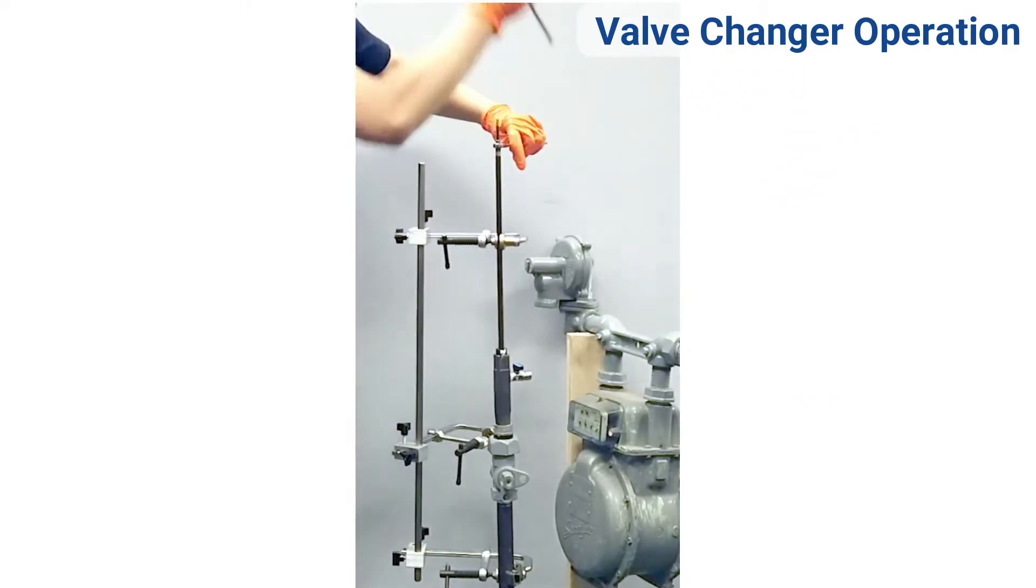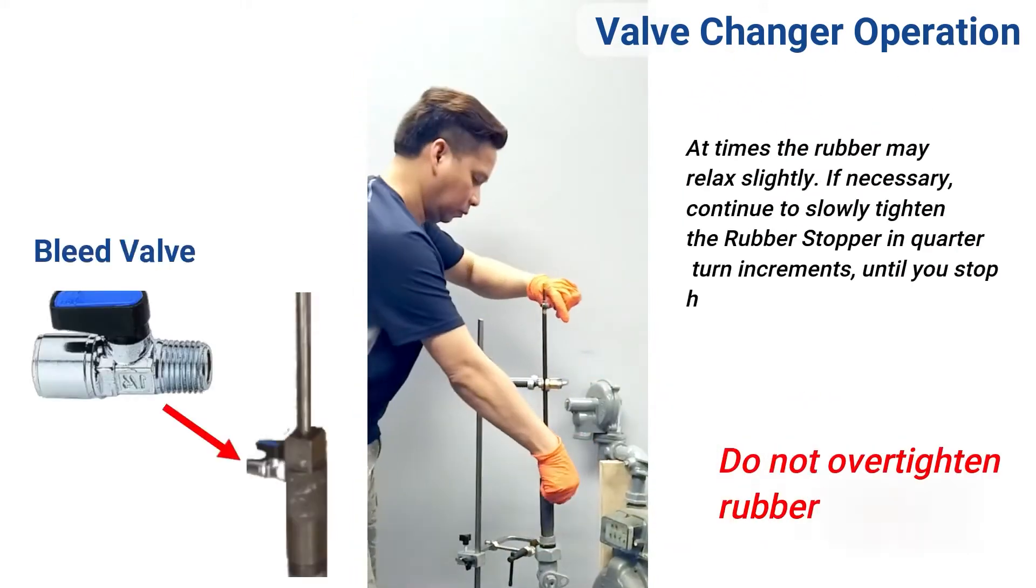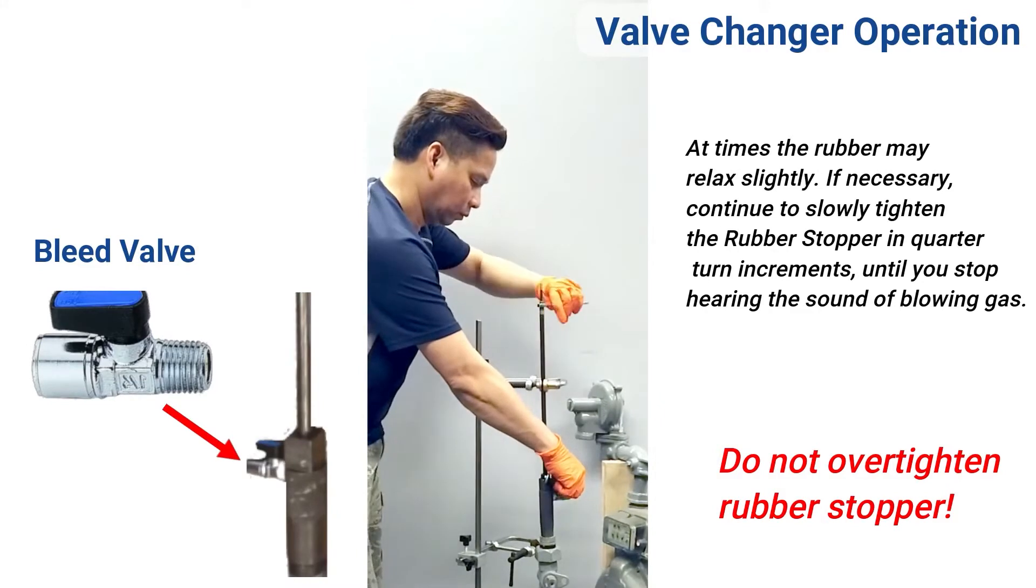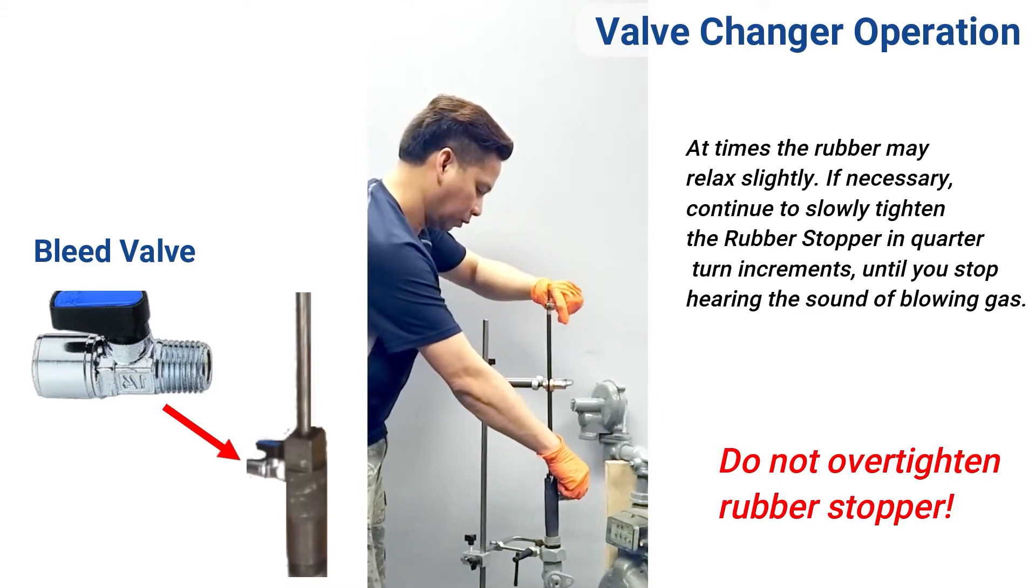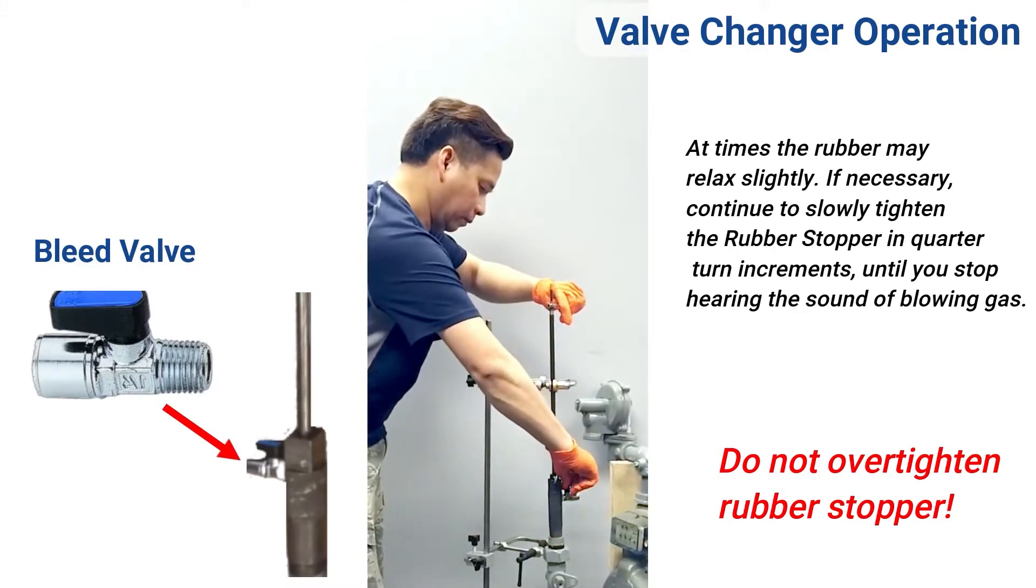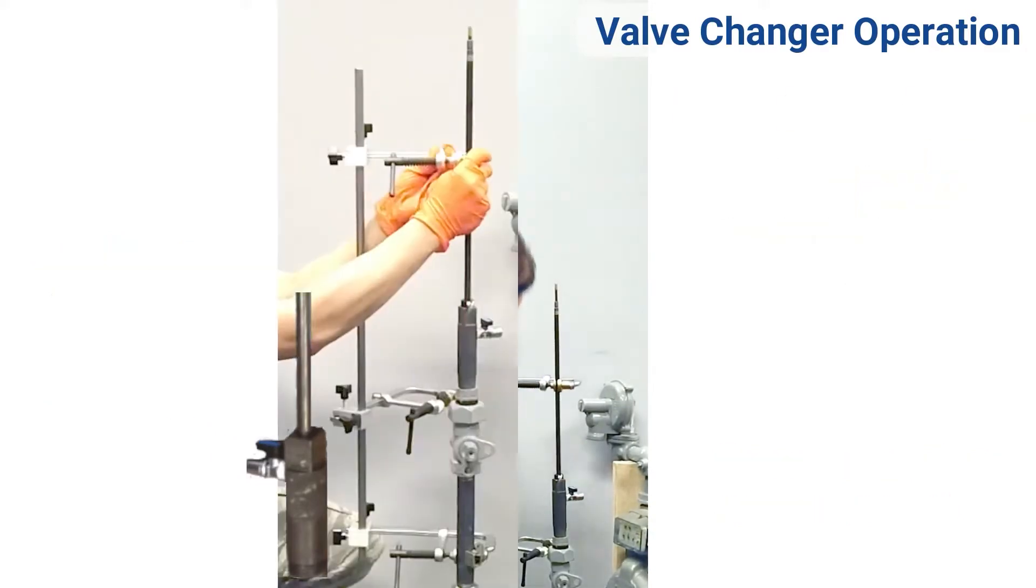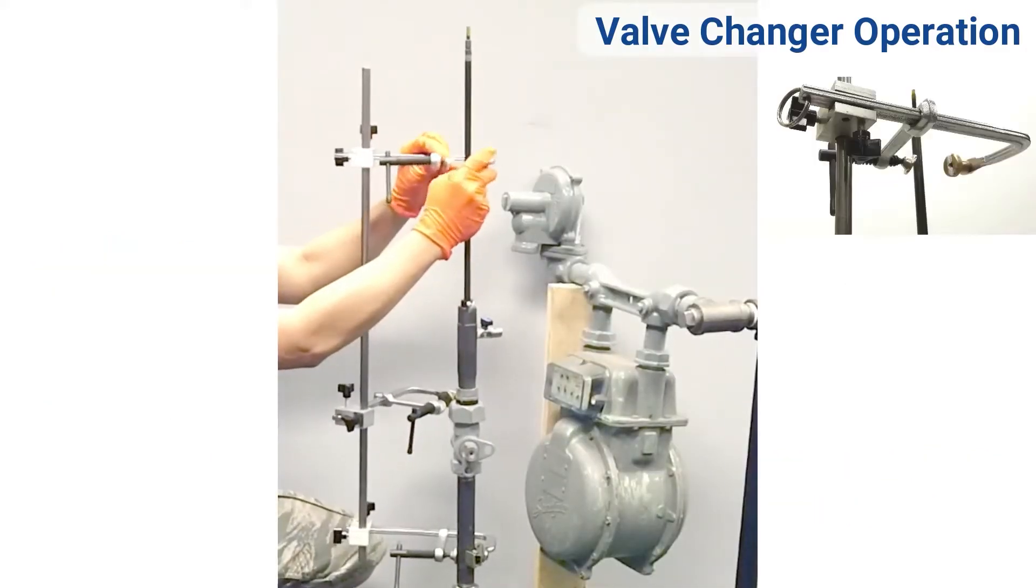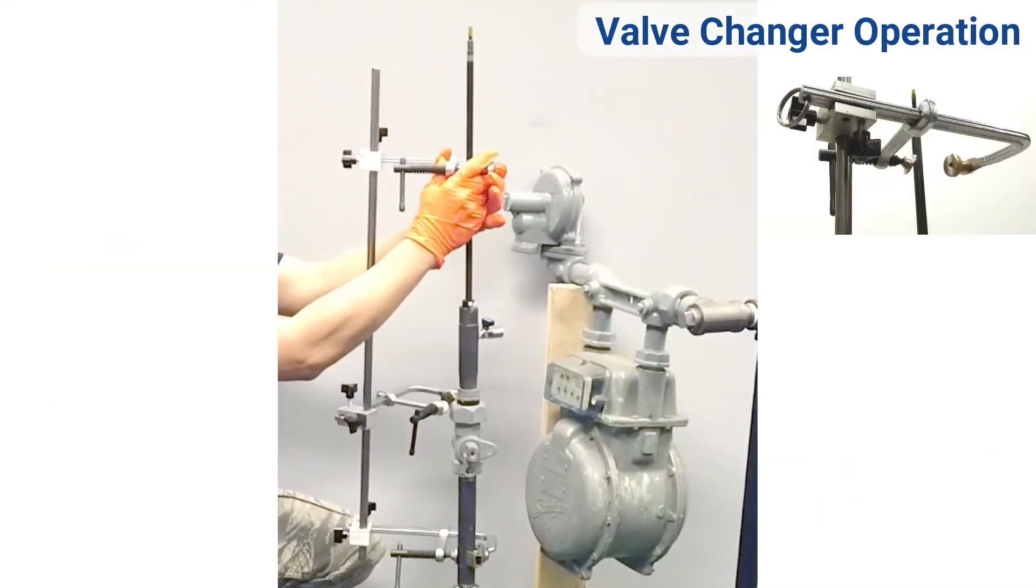Open the bleeder valve. Continue to slowly expand the rubber stopper in quarter turn increments until the sound of blowing gas has stopped. Do not over tighten. Once gas has stopped, fasten the top clamp.